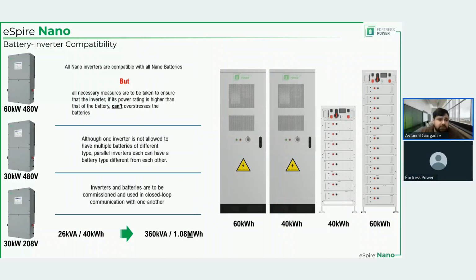So just a quick note about scalability, which I mentioned before. With this compatibility in mind, the smallest system that you can have is a 40 kilowatt hour or 26 kVA energy storage system. That is the smallest configuration. And the biggest configuration will be a 360 kVA inverter bank. That will be 6 60K inverters and 1.08 megawatt hours, which will be 18 60 kilowatt hour batteries, right? So we're done with the summary. Let's look at the ports, technicalities, the environment for installation, and so forth.